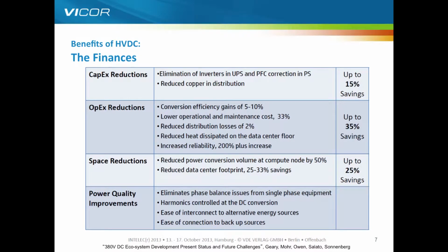In this case it's a data center focused study. When it comes to CapEx, the original building cost, by eliminating the uninterruptible power supply, the UPS, and reducing the amount of copper needed for distribution, you can save 15% on building cost. OpEx comes down to how efficient the system is for the work it does, and the price of electricity in dollars or euros per kilowatt hour. Space reductions, when we talk about data centers, come down to how much functionality per square foot you can achieve - that's a big area there.